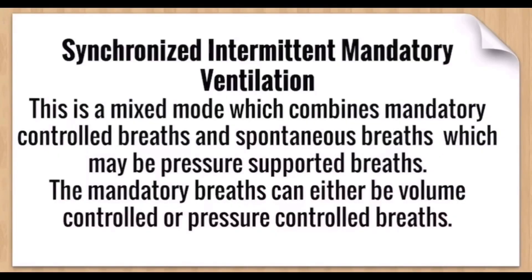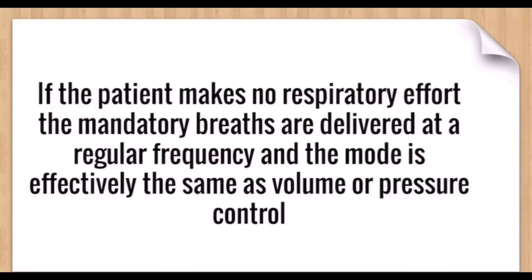Synchronized intermittent mandatory ventilation, known as SIMV mode, is a mixed mode which combines mandatory control breaths and spontaneous breaths, which may be pressure supported breaths. The mandatory breaths can either be volume control or pressure control breaths. If the patient makes no respiratory efforts, the mandatory breaths are delivered at a regular frequency, and the mode is effectively the same as volume or pressure control.